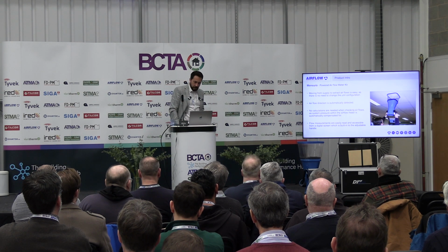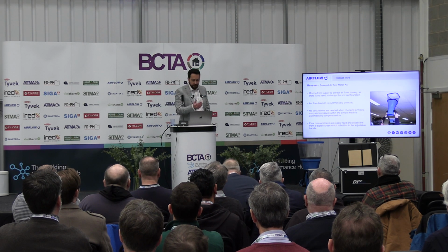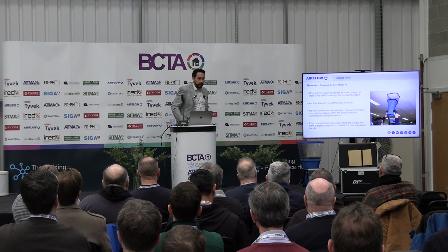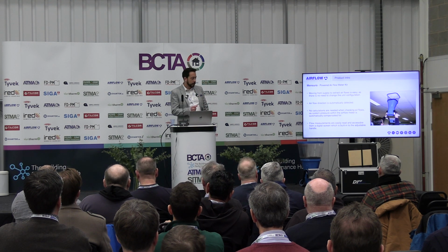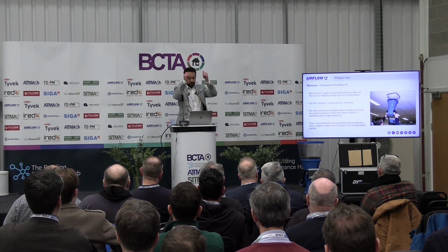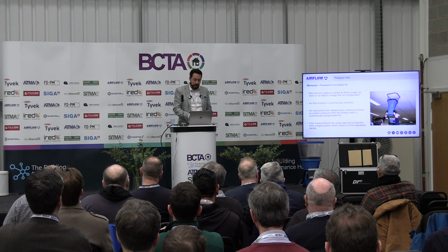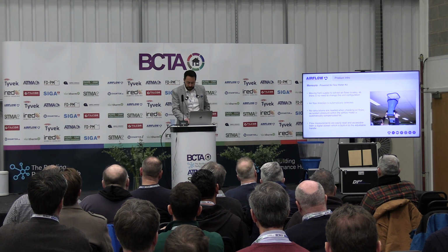So I've actually been out with our own airflow engineers. We go to site, test a number of our fans for our contracted clients to check that they are performing once they're installed. Because there's one thing that the fan says that it can do on the box compared to actually when it's installed. So taking this along to site, after a full day's work, your arms are a bit tired, especially if you're measuring fans that are always installed in the ceiling, because you do have to hold it up there for a few seconds to get the accurate reading. The machine beeps once the reading is confirmed.